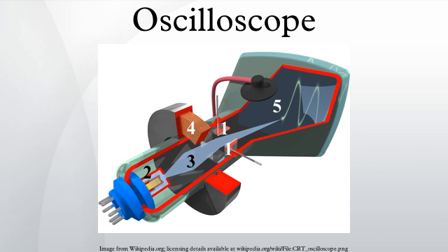The used test equipment market, particularly online auction venues, typically has a wide selection of older analog scopes available. However, it is becoming more difficult to obtain replacement parts for these instruments, and repair services are generally unavailable from the original manufacturer. Used instruments are usually out of calibration, and recalibration by companies with the equipment and expertise usually charges more than the second-hand value of the instrument.